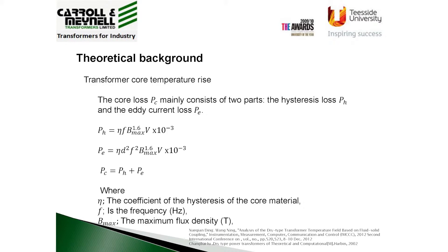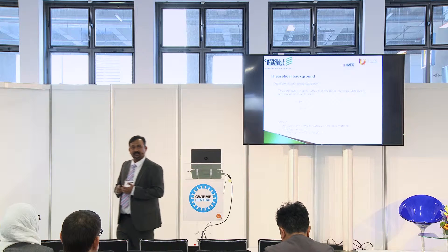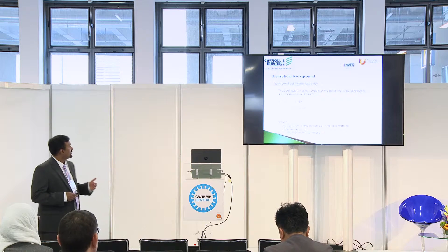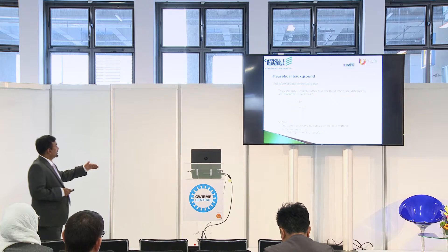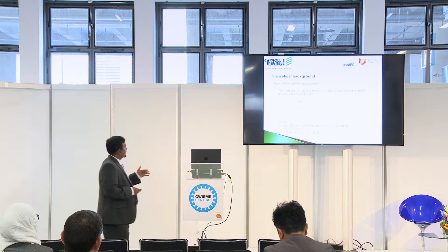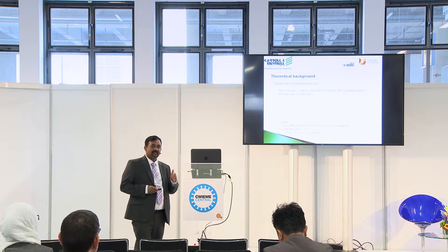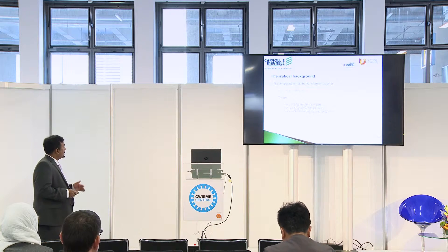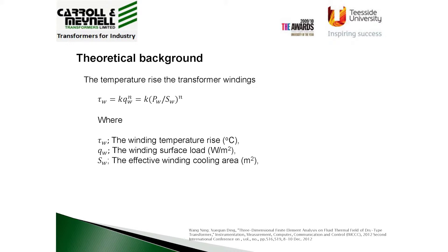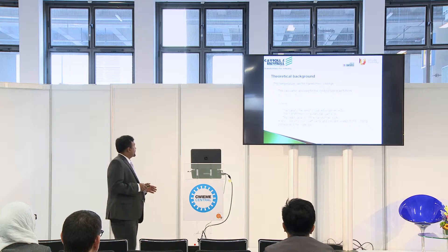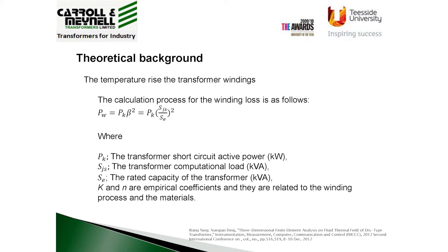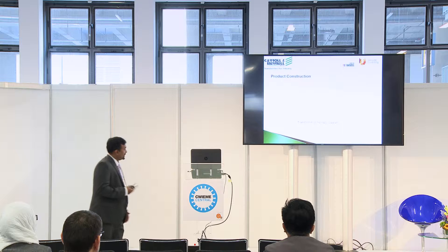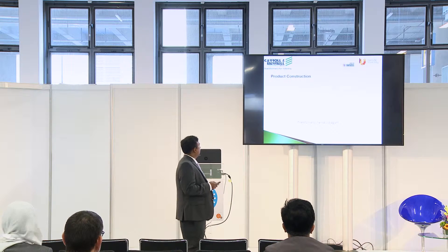We then estimate the core losses — as the previous speaker discussed, manufacturers specify core losses to some extent and there are different techniques to estimate them. You can perform basic calculations of hysteresis and eddy current analysis; the Steinmetz equation is well established and there are several advanced versions of it which we are currently using. Similarly, we can extend the formula to estimate the temperature rise in the windings.